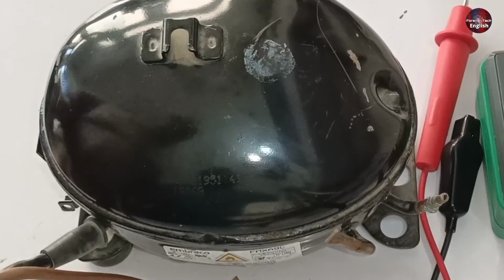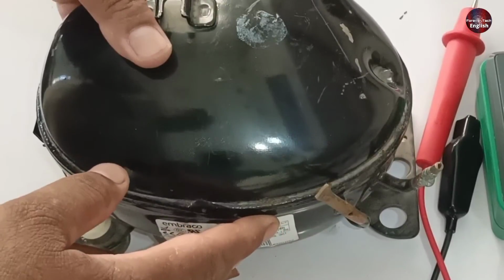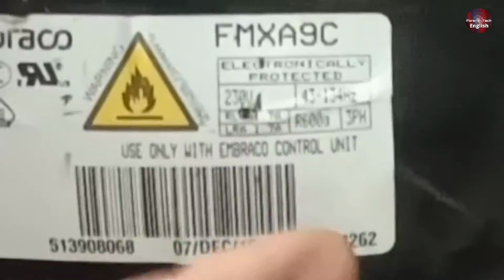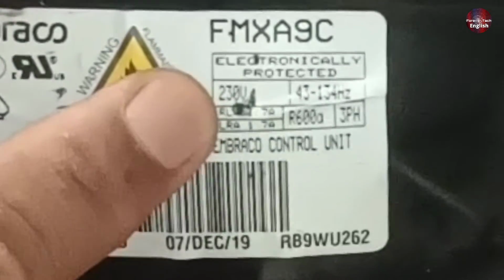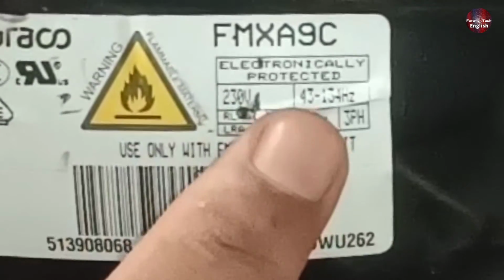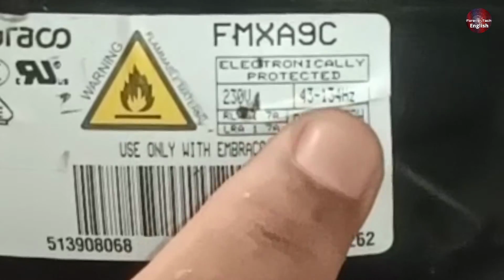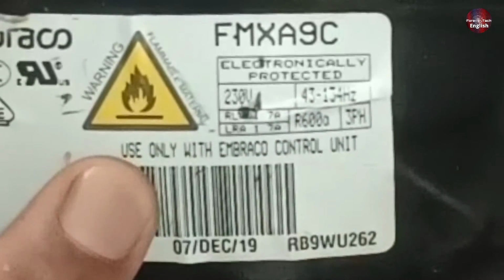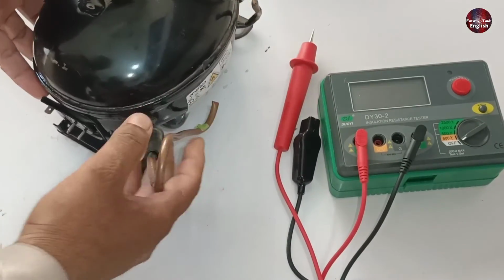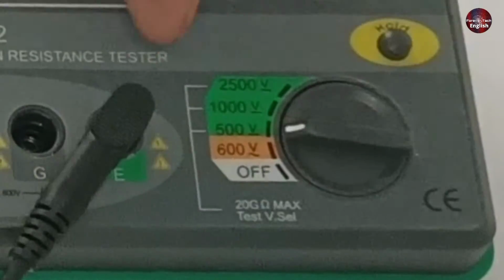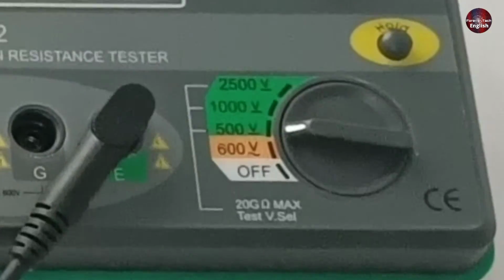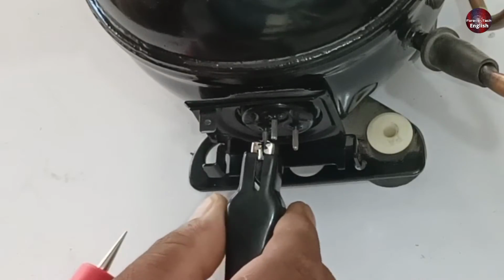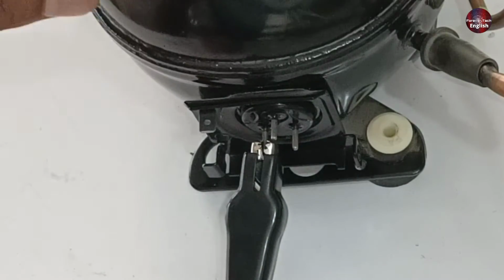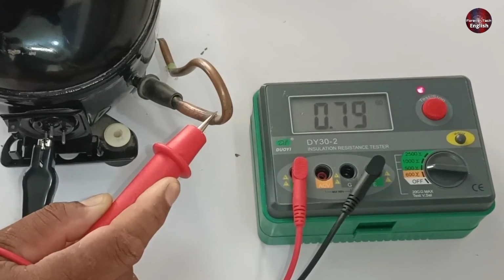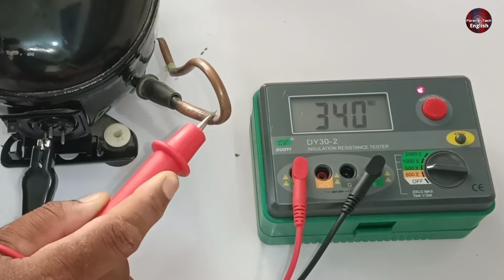Now I have this inverter refrigerator compressor, which is an AC inverter. The maximum voltage range of the compressor is 230 volts. The frequency is 43 to 134 Hz. I will not test it on such a high voltage range from the megger. I have set the rotary switch to 500 DC volts. Attach the first probe with any terminal of the compressor. Now I will attach the second probe to the compressor's body and press the start button.